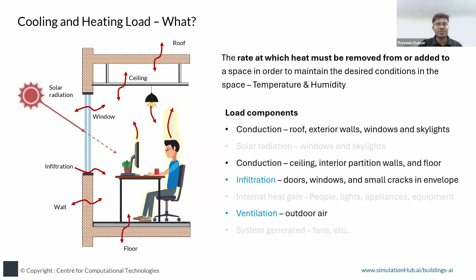So you have certain load components you calculate using MCP delta T formulas, and then you just sum it up and you get the cooling load and peak load, right? Well, it's not like that. You have these many combinations of heat transfer mechanisms going on every second throughout the year, dynamically changing according to your site location and building orientation. So it's not as simple as it looks.